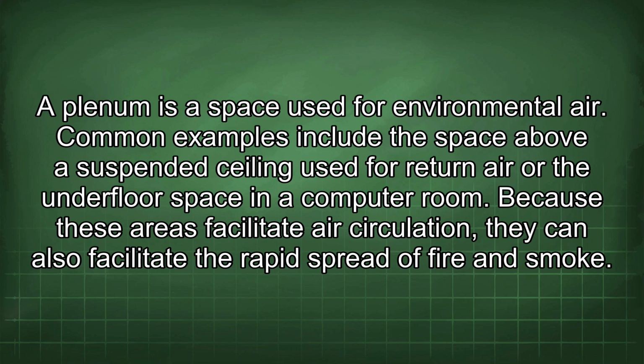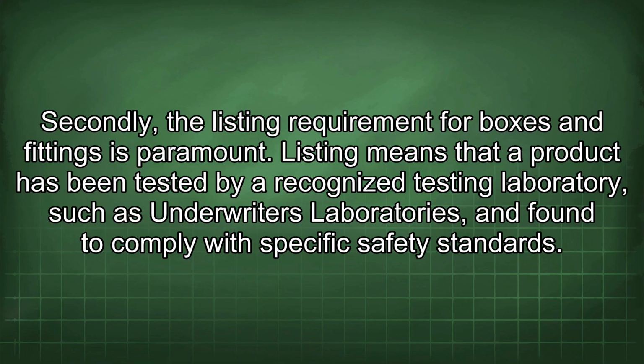Common examples include the space above a suspended ceiling used for return air or the underfloor space in a computer room. Because these areas facilitate air circulation, they can also facilitate the rapid spread of fire and smoke. Secondly, the listing requirement for boxes and fittings is paramount. Listing means that a product has been tested by a recognized testing laboratory, such as Underwriters Laboratories, and found to comply with specific safety standards.